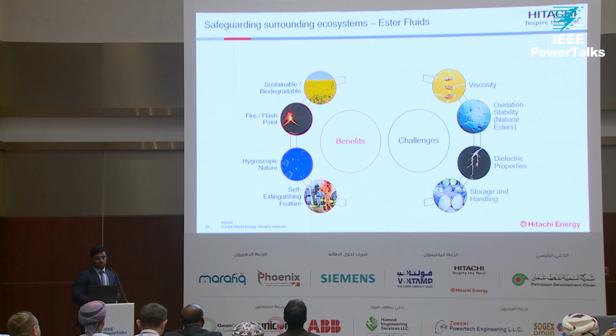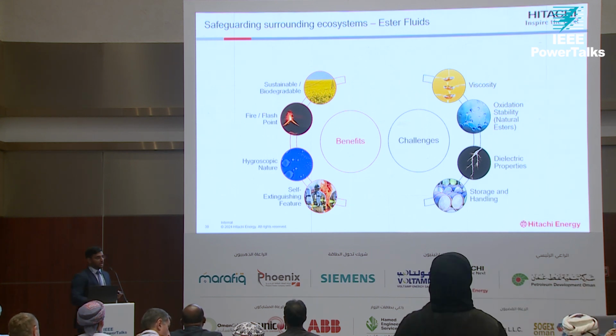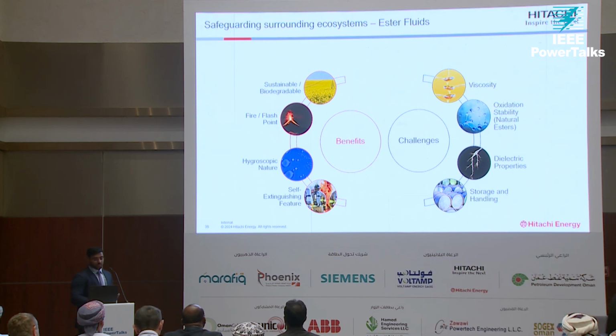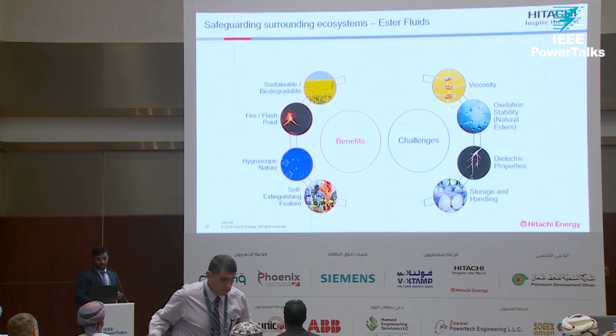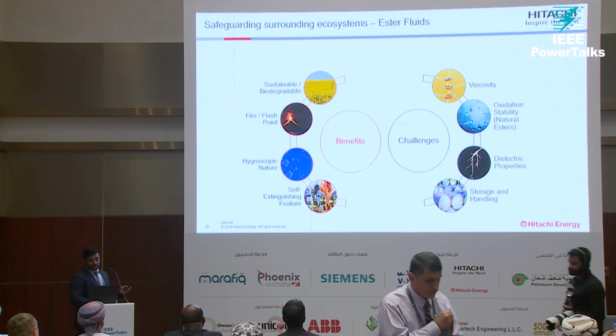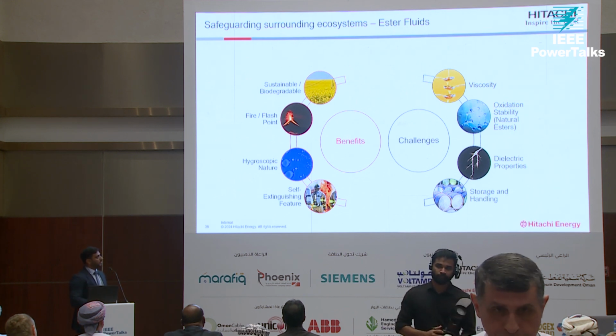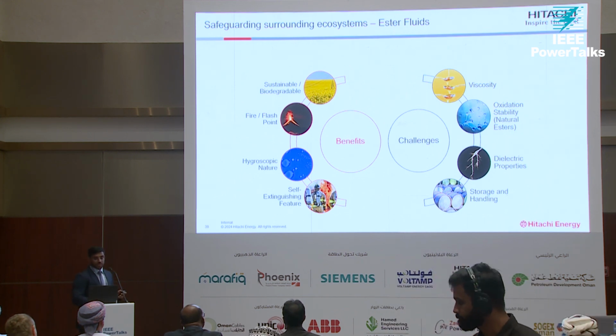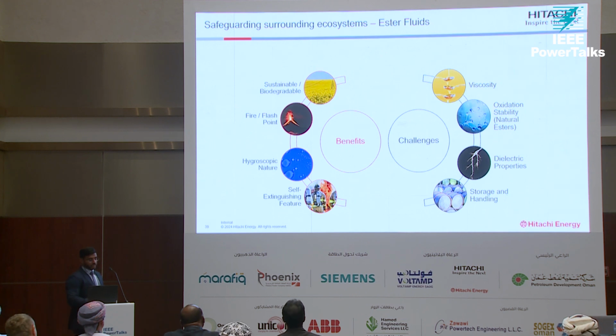When we talk about protecting the ecosystem, one of the main aspects is that mineral oil leakages are a major avoidable risk for environmental impact. Nowadays there are alternative solution fluids available, such as ester oil. These fluids are biodegradable in nature, up to 98% in their natural ester form. With these esters, the main advantage is that the flash point is more than 300 degrees, hence the fire risk is avoidable.